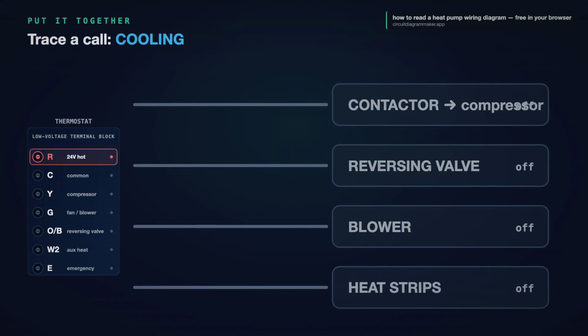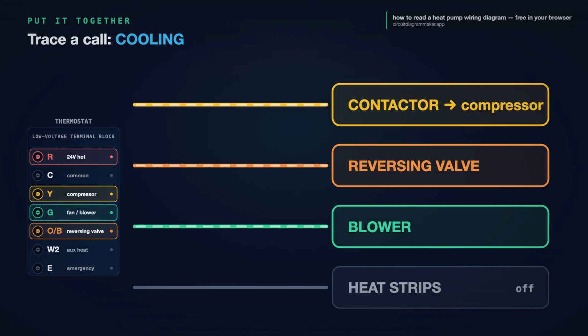Let's put it all together and trace two calls. A cooling call. The thermostat closes R to Y and R to G, and on an O system, R to O. Y pulls in the contactor, O energizes the reversing valve for cool, G runs the blower. Cold air. Now, a heating call.